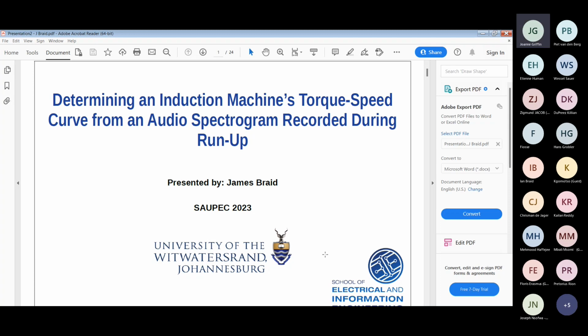In fact, we plug the machine - we do the test from full speed reverse to full speed forwards, take some speed measurements, work out the acceleration, derive the torque, and do some other scaling. Then we have this torque speed curve, which generally matches up with the designed curve, obviously. We haven't had any problems, but we've always found some interesting things which I'll share with you.